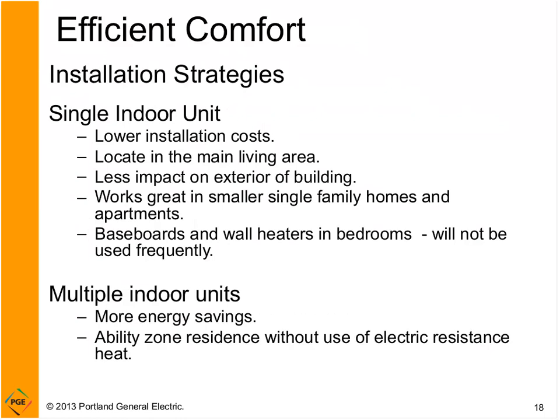There are several installation strategies that can be looked at when you're considering a ductless heat pump system. A single indoor unit is going to offer the lowest installation cost. Every system is going to have the outdoor unit, and then you can choose additional indoor units. This is just one indoor unit, one outdoor unit, so the installation cost is going to be significantly lower. The strategy is to locate it in the main living area. If you have an apartment, maybe you have a living room and kitchen area that's all kind of open, and then some bedrooms down a short hallway. Install the indoor unit in the main living area, maybe in a place where it can send the air down the hallway too to help heat the bedrooms.